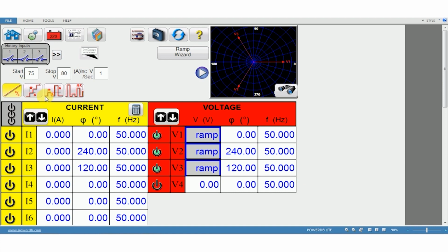The second is called the step ramp. The third is called the pulse ramp. And the fourth is the pulse binary ramp. We're going to connect this kit to an ABB make REL670 relay, where overvoltage is configured for 120%. And we're going to run all four modules to check what is the exact pickup.